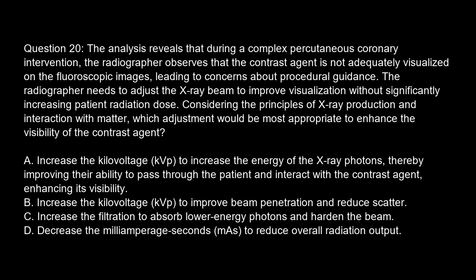Increase the kilovoltage (kVp) to increase the energy of the X-ray photons, thereby improving their ability to pass through the patient and interact with the contrast agent, enhancing its visibility. Option B. Increase the kilovoltage (kVp) to improve beam penetration and reduce scatter. Option C. Increase the filtration to absorb lower energy photons and harden the beam. Option D. Decrease the milliampere-seconds (mAs) to reduce overall radiation output. The correct answer is B. Increase the kilovoltage (kVp) to improve beam penetration and reduce scatter.